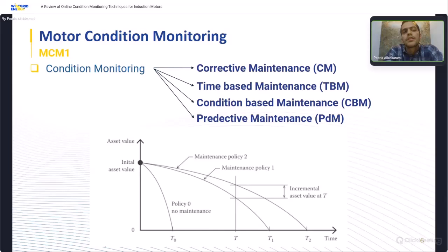ones with a condition monitoring system. Sudden breakdowns can cause secondary damage to nearby components, threaten personal safety, and cause environmental incidents, which are the causes of this high risk. For this reason, corrective maintenance is suitable only for low-cost or non-critical equipment where the expense of monitoring or preventive action usually outweighs the cost of the repair.